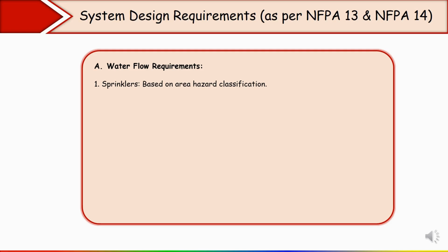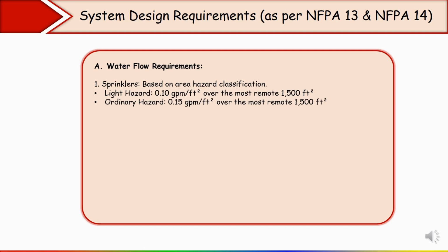If it is an ordinary hazard, it is 0.15 GPM per square feet over the most remote 1500 square feet. Correct? Same way, you can go for the extra hazard. Okay, it is given here. For light hazard 0.1 and for ordinary 0.15 GPM per square feet.